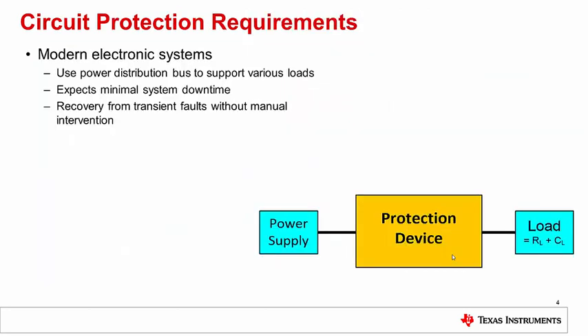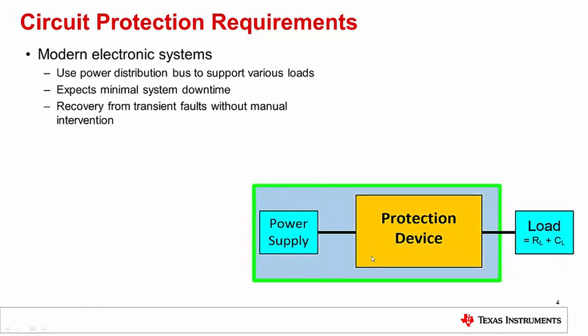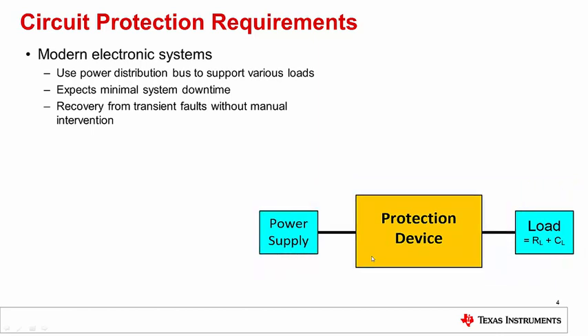These electronic systems use a multi-voltage power distribution bus to support various loads. One of the major expectations is minimal system downtime during any transient abnormal events such as overload or short circuit conditions. Not only that, the system should recover from transient faults without any manual intervention. For example, any overload event can affect the power quality of the connected bus and eventually affect other connected loads in the same bus. So today's system designers use protection devices at the load side or supply side, or sometimes at both ends, to protect systems against faults.